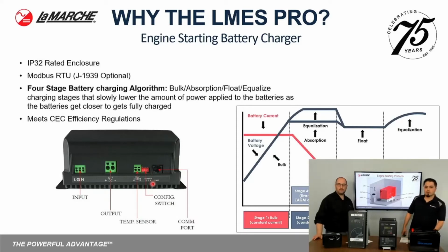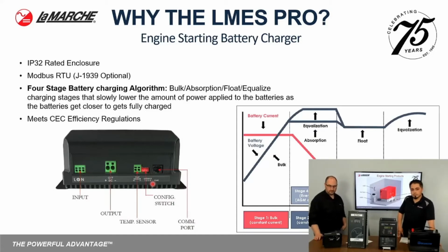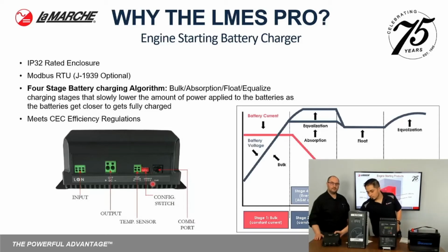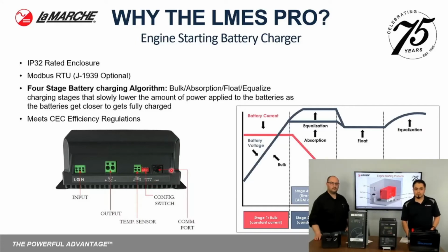So the LMES Pro is an IP32 rated enclosure. That's one of the big factors in pushing the LMES Pro. Another one being that it comes standard with Modbus RTU communication. As an option, or to improve on that Modbus communication, we also have a J1939 that'll be available within the same port. As you see here, this would be utilizing the same port, the COM port, for RTU or J1939. Obviously, one has an option to add that J1939 connection. This is a little bit more of a standard feature nowadays in the engine starting market. There are a lot of diesel engines that are running off of J1939.